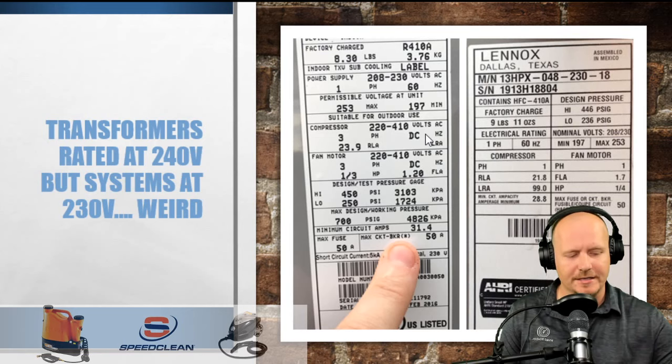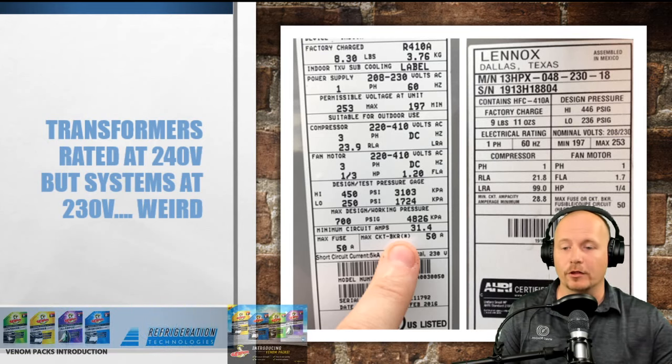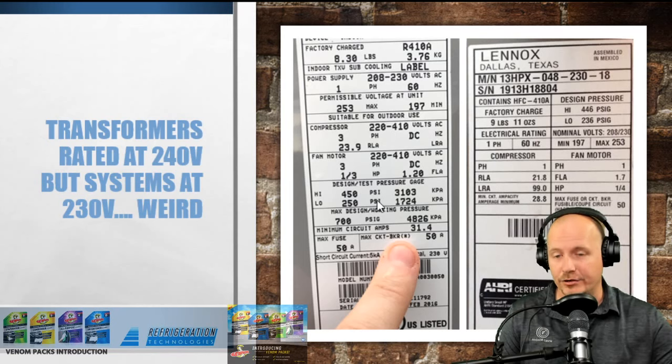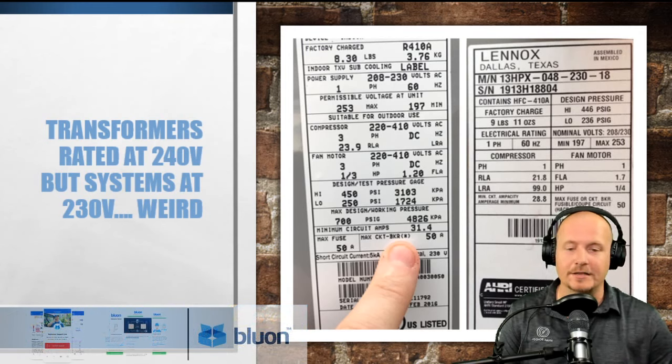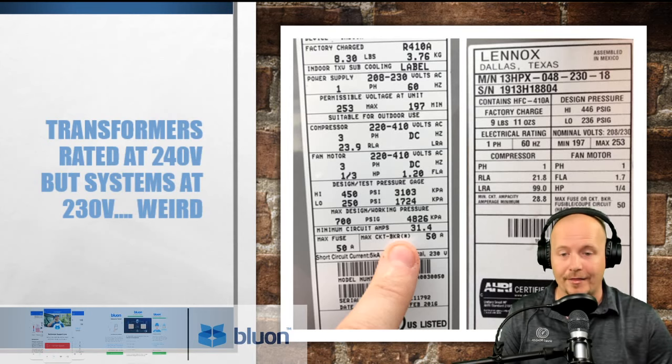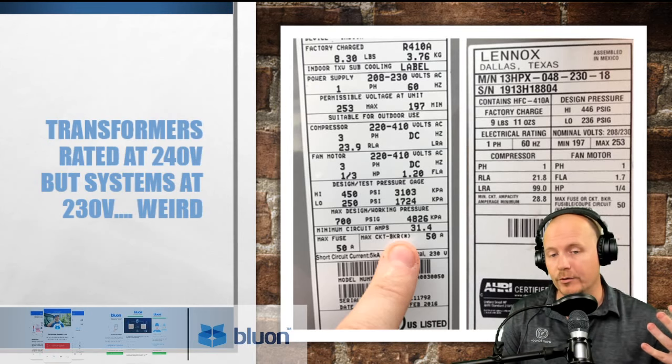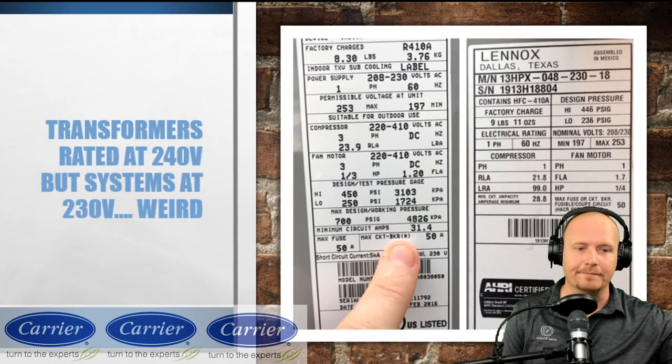Joe had actually seen this, and maybe you can mention this, Joe. In some cases where the low voltage controls were having issues, the utility was driving up the voltage. I think he said he had seen a transformer rated at 230 rather than 240, and that would definitely do it if you had an incoming voltage of, say, 248 or 250.